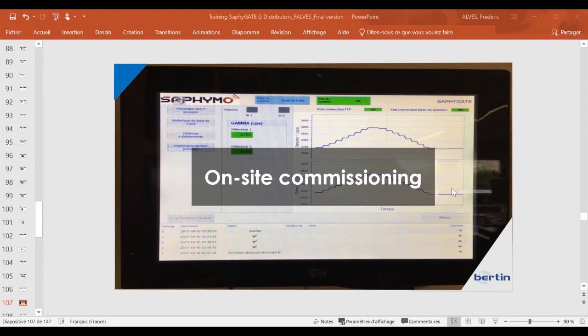But then we know it depends on each site. Due to the environment, due to where the system is installed, due to other parameters, sometimes you have to set the alarm threshold higher than 5 sigma. You can put 6 or 7 sigma depending on each site, but for sure you cannot put a parameter higher than 5 sigma at the beginning of the installation.